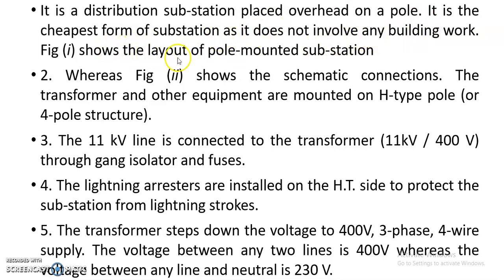Figure 1 shows the layout of the pole mounted substation, whereas figure 2 shows the schematic connection or single line diagram of the 11 kV pole mounted substation. The transformer and other equipment are mounted on an H pole or 4 pole structure. The 11 kV line is connected to the transformer through the gang isolator and fuses. The lightning arrestors are installed on the HT side in order to protect the substation from lightning strokes or lightning overvoltage.